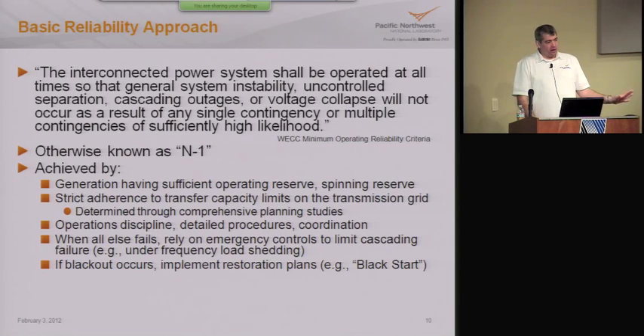This is both done at the operating and planning time horizons. So in operations, they're doing this with their state estimation process and, in real time, calculating what the credible contingencies are and presenting that information to operators. That loop might take 5 minutes for that type of calculation to occur. But even on the planning side, you're looking ahead, and so engineers and planning departments are looking at 2 years from now and studying what the possible load and generation patterns might be, making sure that there's enough infrastructure in place to be able to handle that. People call that N-1. That's kind of the shorthand. So you have N components.